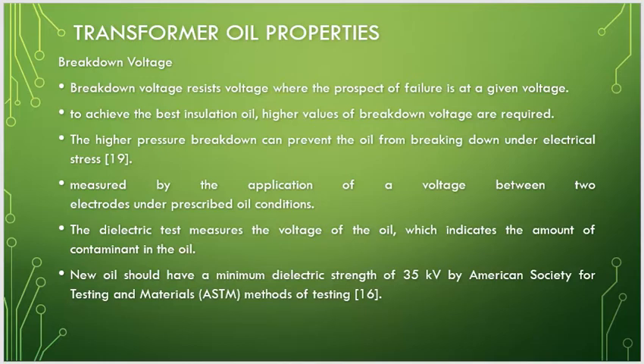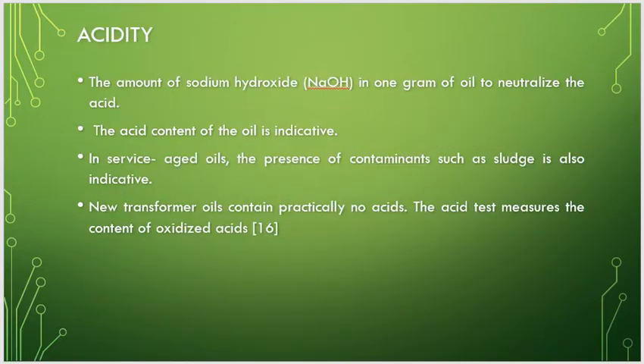And for transformer oil properties, there is breakdown voltage. It is the probability of failure at a given voltage. To achieve the best insulation oil, a higher value of breakdown voltage is required. It can prevent the oil from breaking down under electrical stress. It is measured by application of voltage between two electrodes under prescribed oil conditions. The dielectric test measures the voltage of the oil, which indicates the amount of contaminant in the oil. New oil should have a minimum dielectric strength of 35 kV by the American Society for Testing and Materials method for testing. Then for acidity, the amount of sodium hydroxide in 1 gram of oil will neutralize the acid.